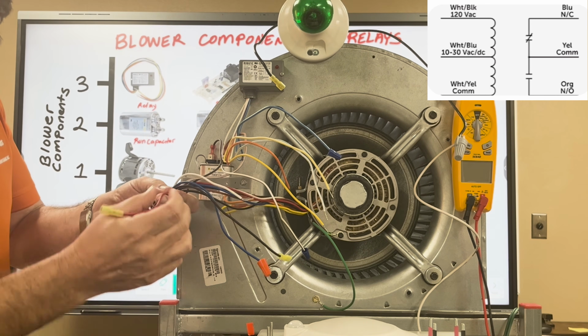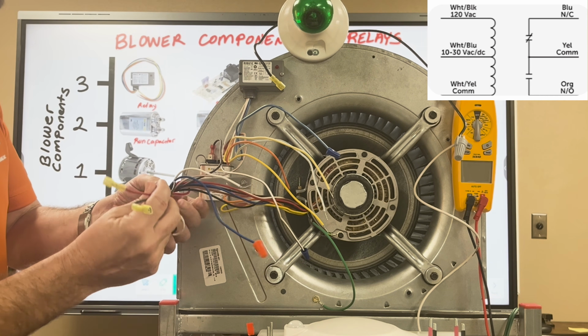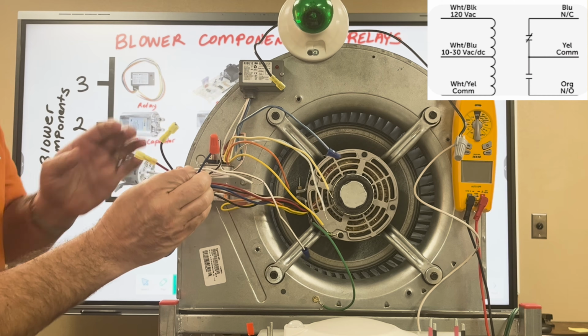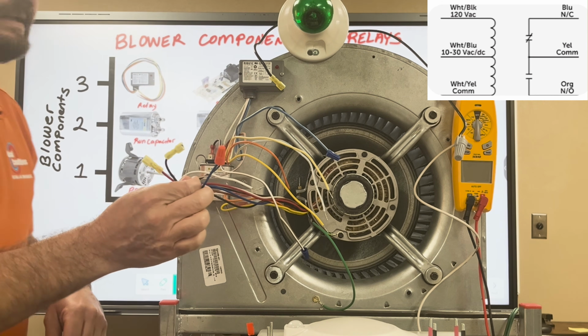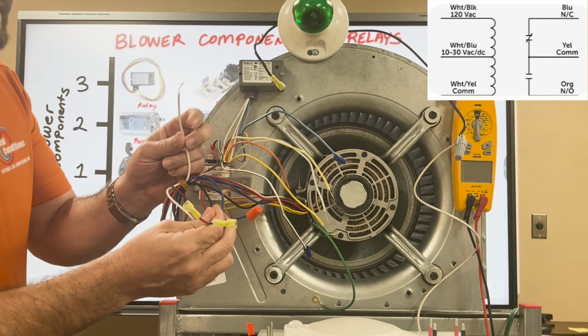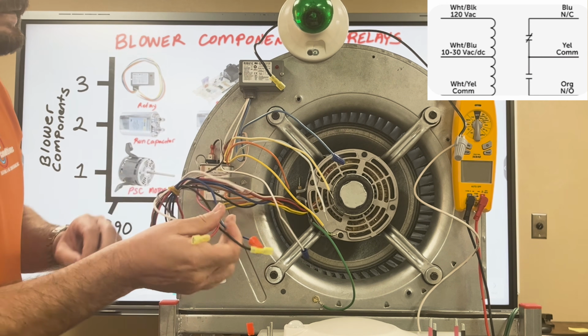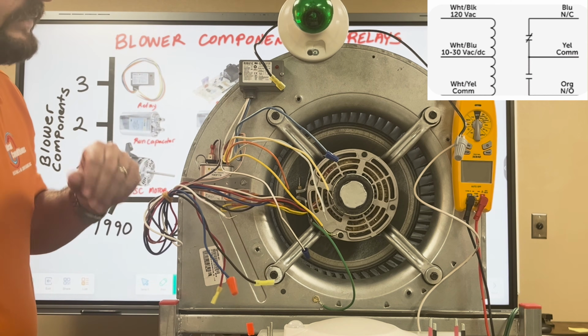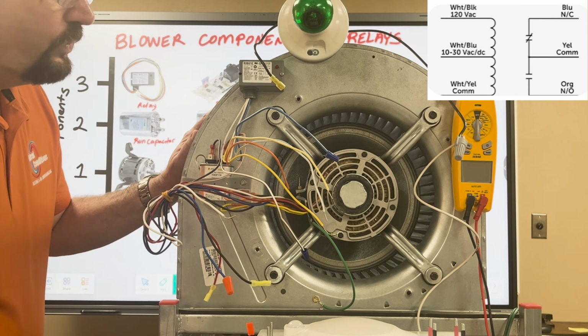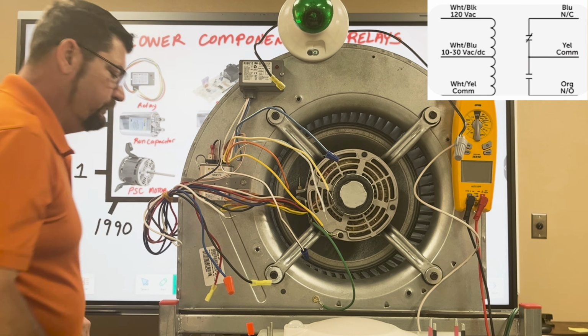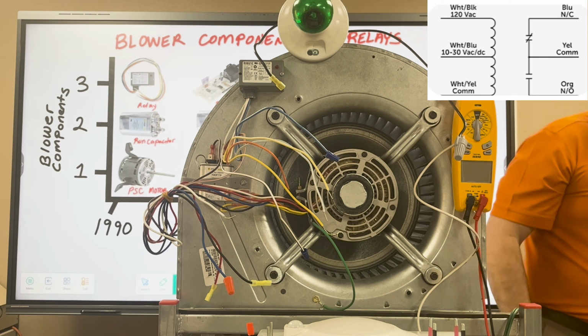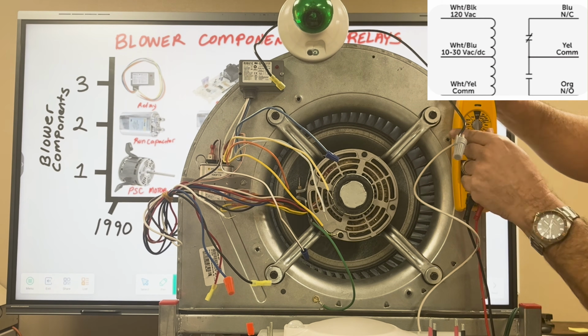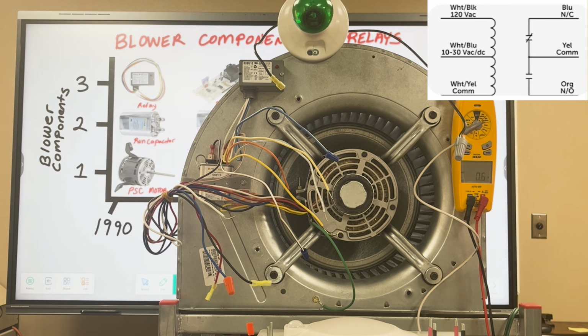We have red for low, black for high speed, and blue, which I have wire-nutted off here, is for medium speed. And the other one is the other leg of power. As long as we put 240 volts of power on it, that motor will run. So let's go ahead and go to the meter and demonstrate our power for transparency. We're going to turn the backlight on, and you'll see right now we're reading 0 volts.